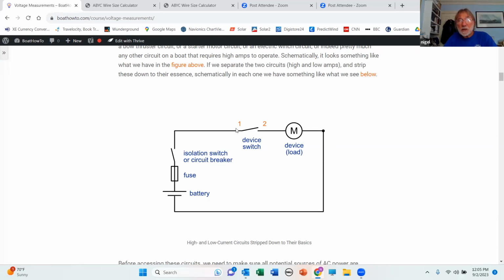If, however, we get a sudden change in the voltage drop, a sudden reduction, between the last place we were at and the next one, we've got some resistance. It's probably bad connections in the circuit, corroded terminals or whatever. And that way we can trace those parts of a circuit that are creating unwanted resistance and sort them out. But this test only works if you can load the circuit. It's like a stress test for a bank. The circuit's got to be loaded in order to create the voltage drop so that we can then track down where the voltage drop is.